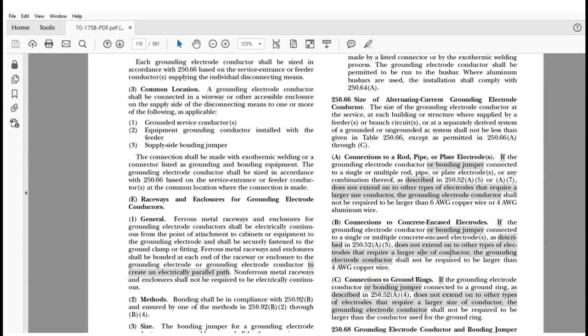Now, this would probably be a proposal by somebody or public input in the 2020 edition to add aluminum here, but we'd have to do some work on where that connection would be made. I think we allow that extension of that rebar to come above the earth. So basically, if it extended up 18 inches, why couldn't you make that connection with a properly listed fitting? But anyway, that has some work to be done, but you could do it. So there is really no change in these two, except they removed the requirement for the sole connection.